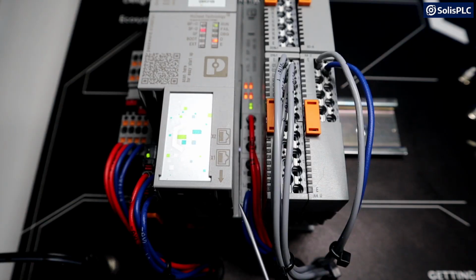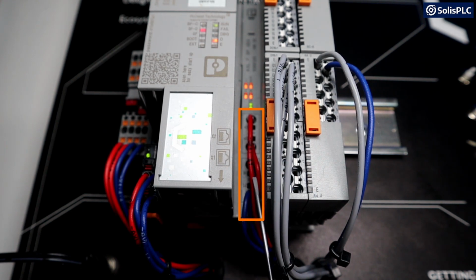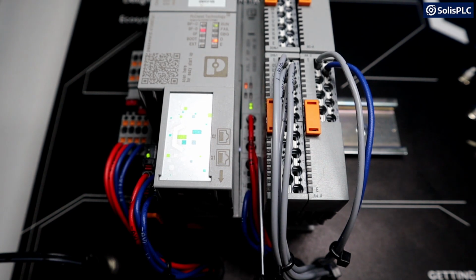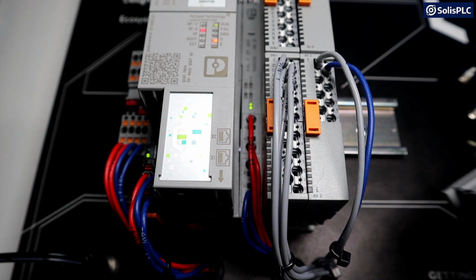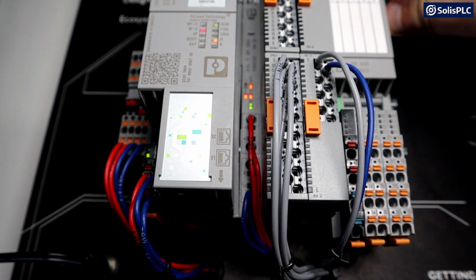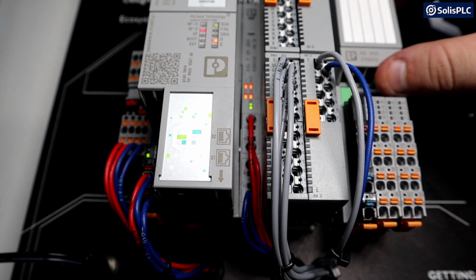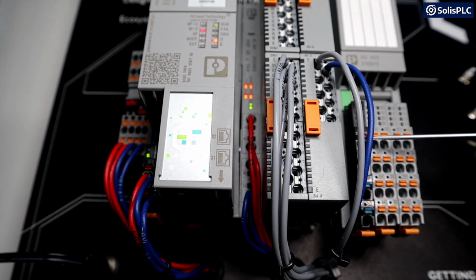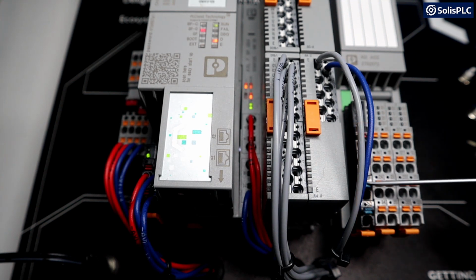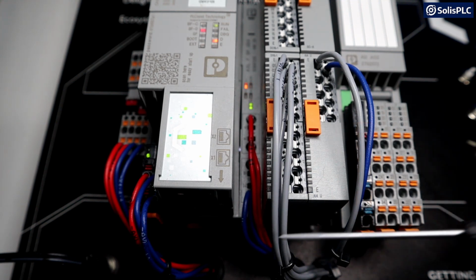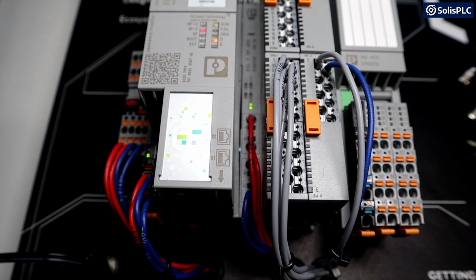The other important thing to notice is that the I/O module also requires power, which will be taken care of for you on the starter kit, but something to pay attention to if you're going to assemble your own system. The PLCnext does not provide power over the backplane. I have an example of a different module, so you'll notice that the form factor is slightly different than the one on the kit, so you also need to provide power to this specific module within the red and the blue marked slots. Those are once again going to take 24 volts VDC.